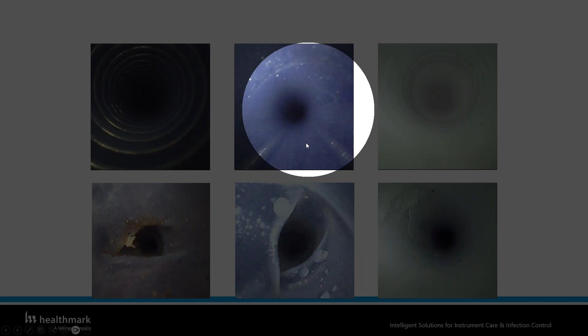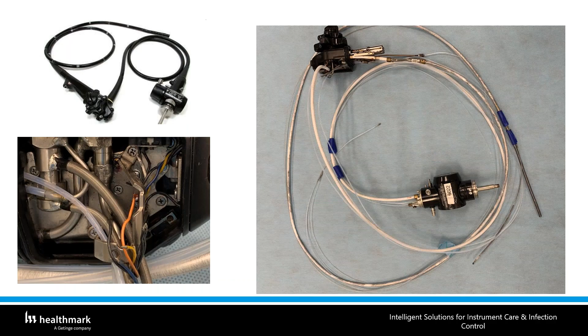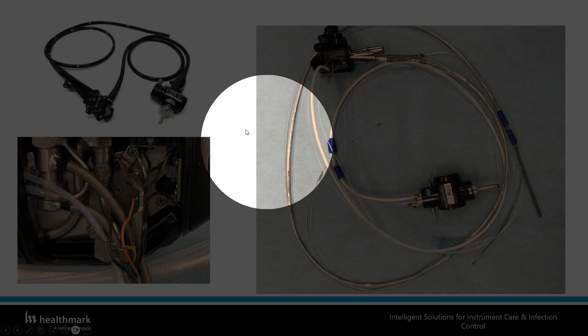And here is another one, the same on top: a good versus a damaged endoscope. These damages, for example the kink, are in the inside tubing that you do not see from outside. So when I look at this endoscope, I would not be able to see the damages, because they are usually on the Teflon tubing, and the outer plastic shield masks that Teflon tubing, so you won't be able to see it. So it's important that you be able to look inside the lumens and see what's going on.